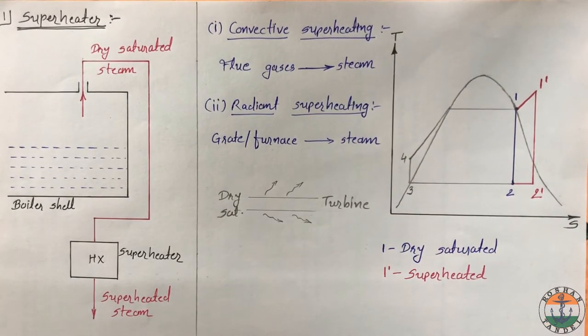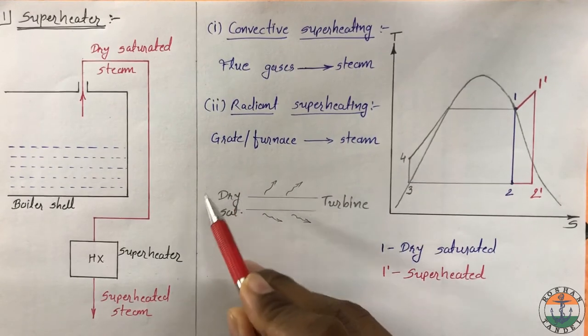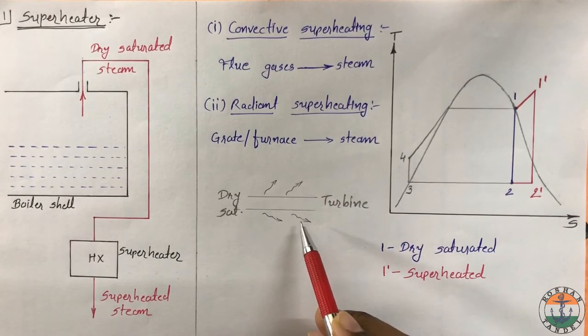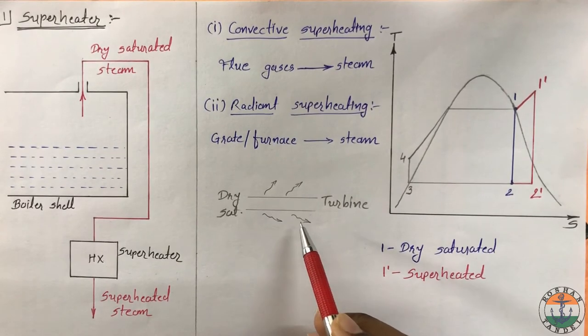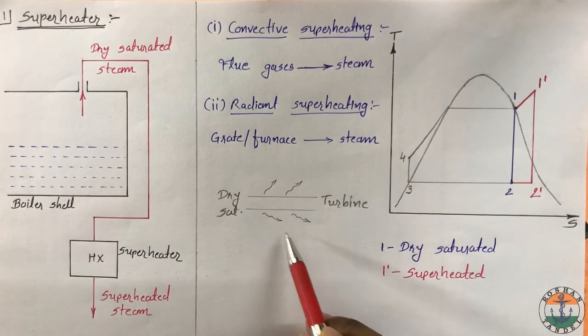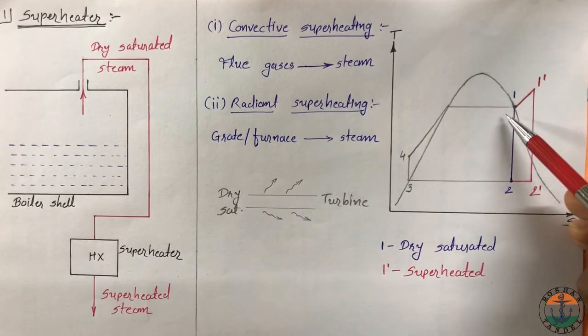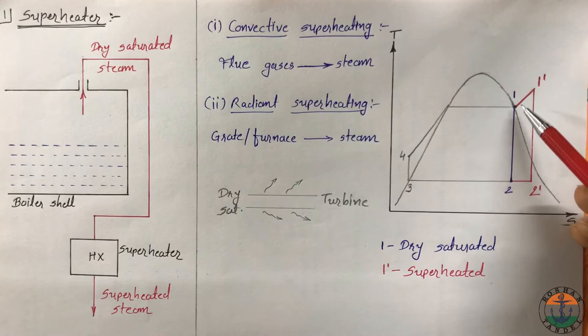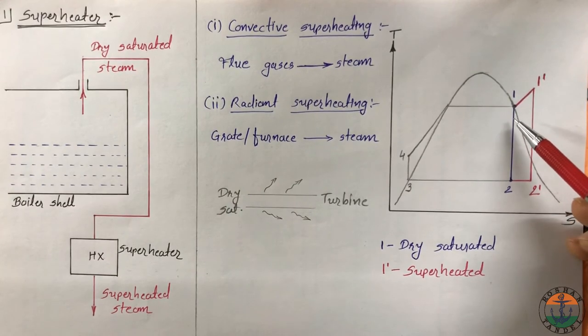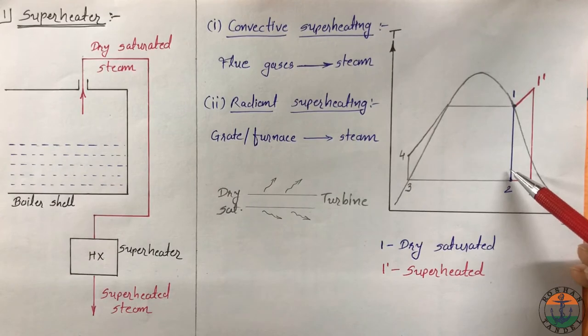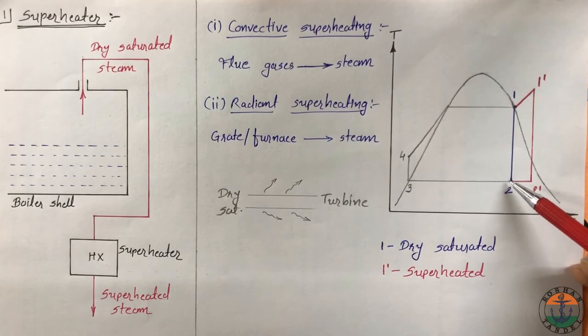Assume that the output of the steam is dry saturated. Now, if you supply this dry saturated steam to the turbine via pipeline, some steam particles may get condensed because of heat transfer to the atmosphere. Even if you get dry saturated steam at the inlet of the turbine, the moisture content during expansion increases friction and erosion of turbine blades.